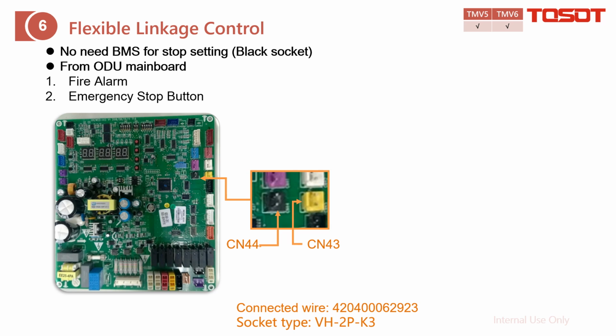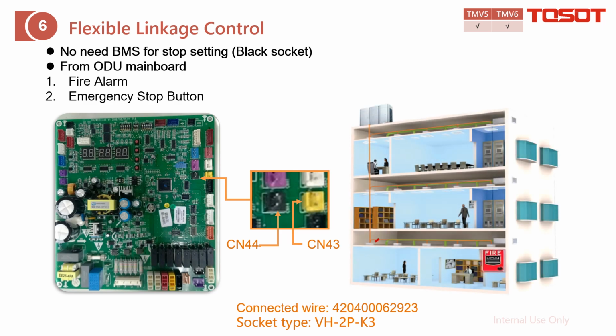Flexible linkage control. That means on the outdoor unit, there is a socket. No need for the BMS. You can achieve the emergency stop, which means you can link to the fire alarm or the emergency stop button to achieve this. For example, in the building, you just install the GMV system and also link a fire signal to the outdoor unit. Then, if the fire alarm happens and is detected by this fire alarm signal, you send it to the outdoor unit, then the system will shut down immediately.